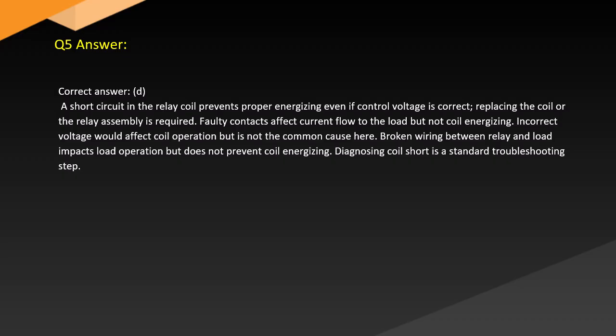Answer. Correct answer: D. A short circuit in the relay coil prevents proper energizing even if control voltage is correct. Replacing the coil or the relay assembly is required. Faulty contacts affect current flow to the load but not coil energizing. Incorrect voltage would affect coil operation but is not the common cause here. Broken wiring between relay and load impacts load operation but does not prevent coil energizing. Diagnosing a short is a standard troubleshooting step.